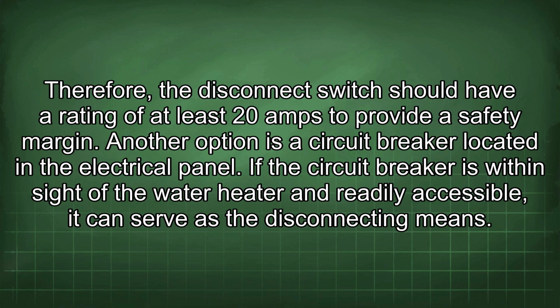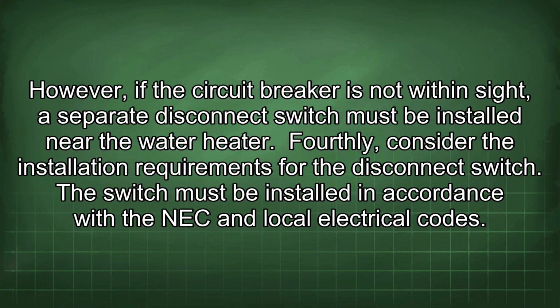Another option is a circuit breaker located in the electrical panel. If the circuit breaker is within sight of the water heater and readily accessible, it can serve as the disconnecting means. However, if the circuit breaker is not within sight, a separate disconnect switch must be installed near the water heater. Fourthly, consider the installation requirements for the disconnect switch.